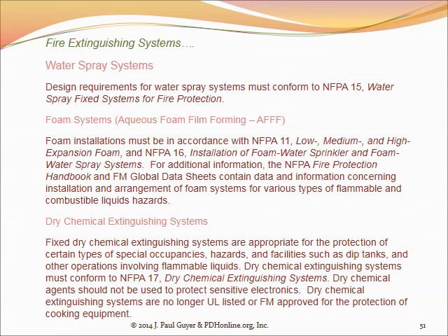There is a class of extinguishing agents called aqueous film forming foam, or foam systems. These are used frequently in places like aircraft hangars, places where there's a lot of fuel of some sort, I mean gasoline, diesel, things like that. The reason is that you can't use water to extinguish a fire with a petroleum fuel like that, because the petroleum fuel is lighter than the water. It will just float on top of the water and keep burning.